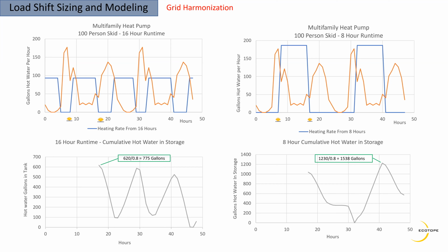If you look at that 16-hour runtime, it's about 95 gallons per hour, and we're making it for about 8 hours. So you can see that we can start to shift around when we use the heat pump and when the loads are. The curve on the bottom is the cumulative hot water in storage, essentially a modeling of the net effect of how much storage is left. After you get a peak draw, you run and make a bunch more heat. Where the curve on the bottom ramps up, that's where we're making hot water and recharging the thermal battery. And then it discharges. By doing this, we can establish how big the storage needs to be.